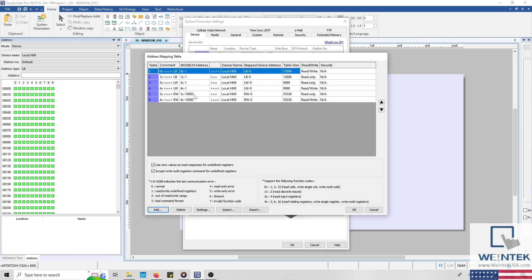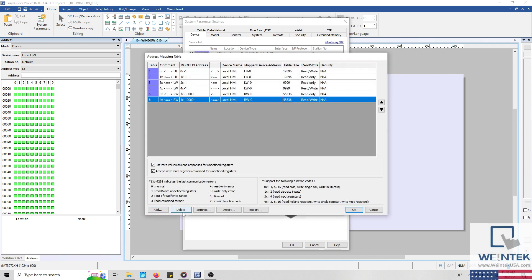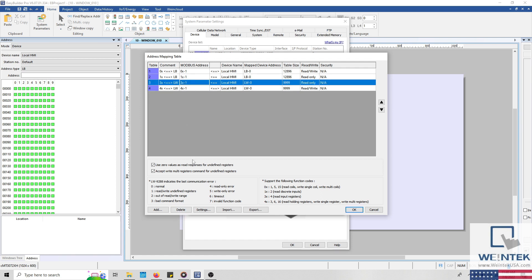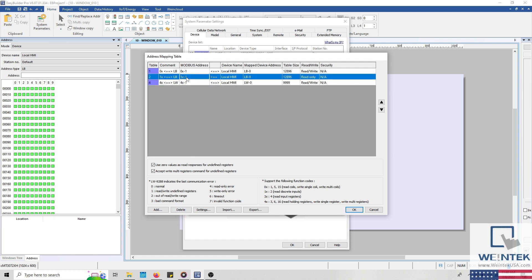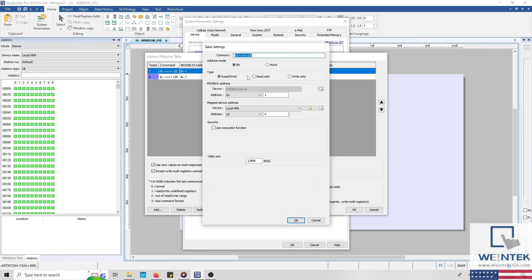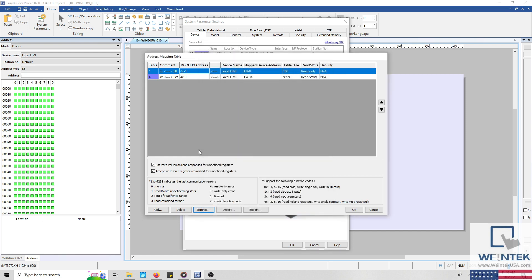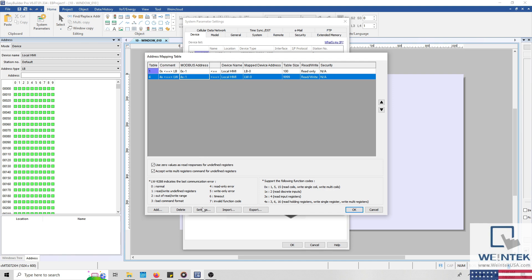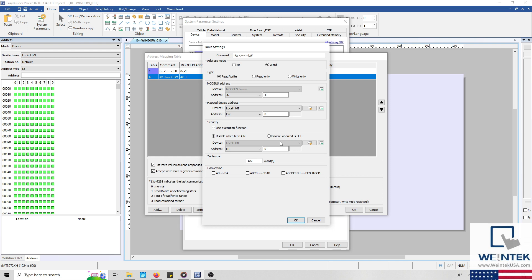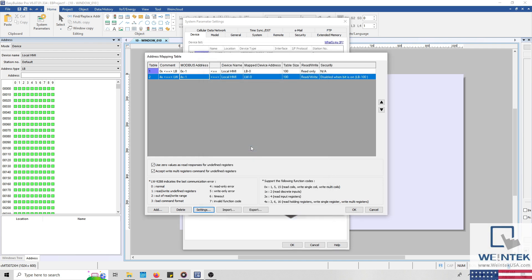To begin, I'm going to delete table 6, 5, 3, and 2. Then, I'll reconfigure the size of table 1 to 100 bits, and enable Read Only. In table 4, I'll reconfigure the size to 100 words, and enable Use Execution function. This will allow the HMI to restrict write access based on the state of a predefined bit. I'll configure the execution bit to LB100, and click OK to save my current configuration.